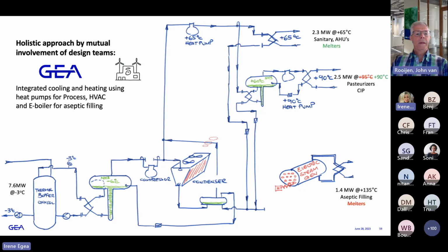So we still have a refrigeration plant on the low temperature side, but as you can see, we have only one condenser not dissipating that much heat anymore, and a large amount of the heat is now taken away by the heat pumps. The heat pump of 65 degrees is generating 65 degrees water, and it's also the feeding of the 90 degrees heat pump. And to still be able to generate steam, an electrical steam generator was indicated.